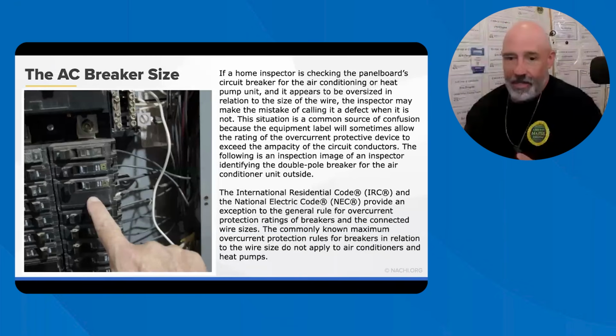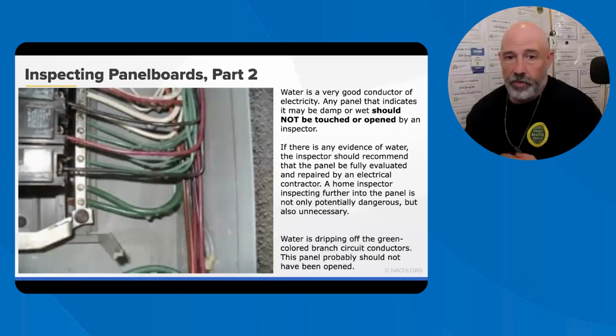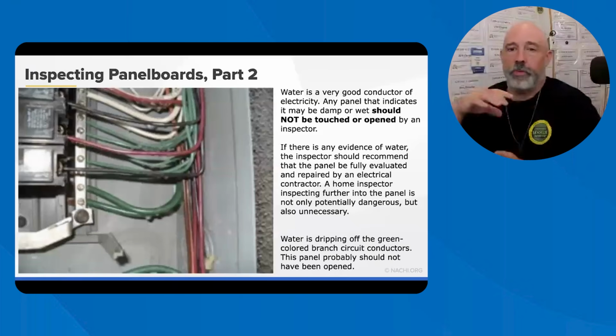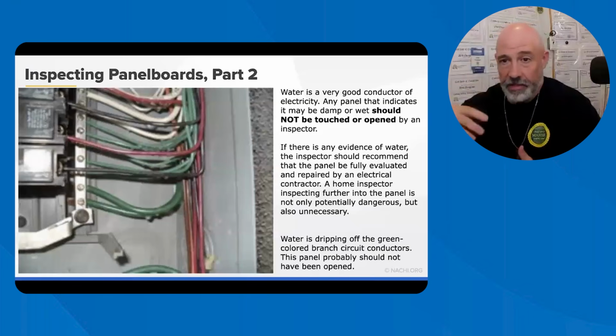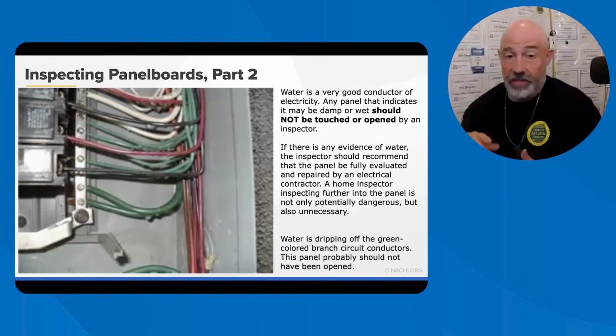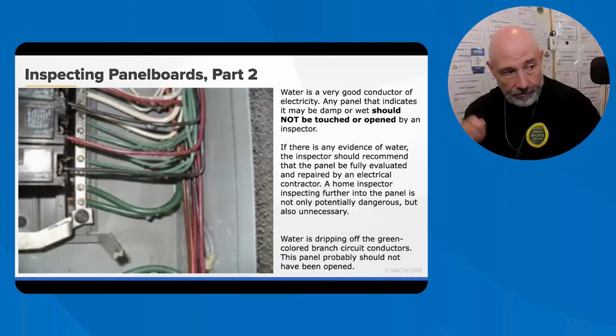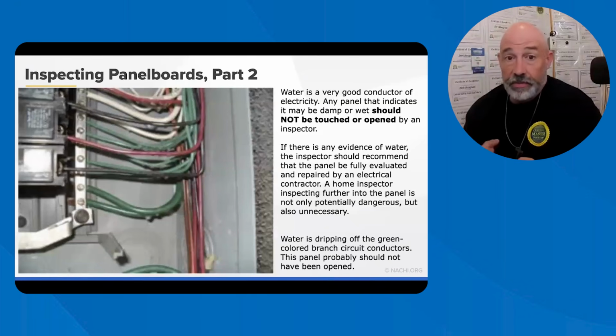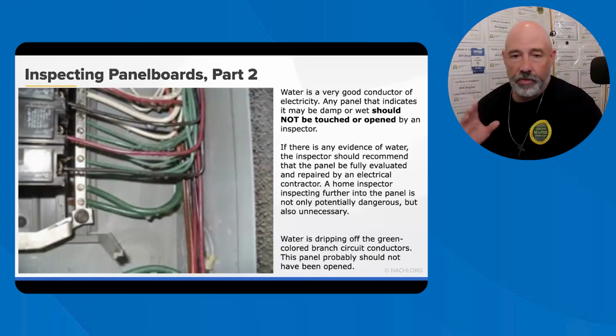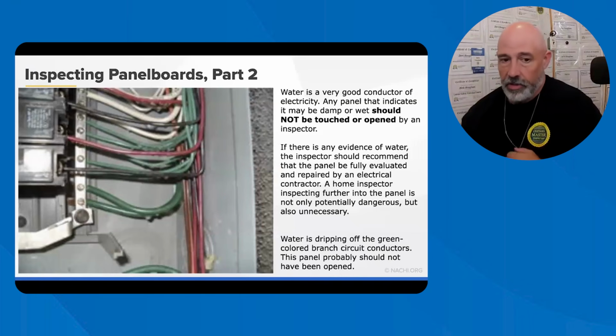But the NEC and the IRC both have stuff for electrical panels, and you can read it on your own if you want, or ChatGPT it or AI it or whatever you want to do. Even before thinking about touching or inspecting or removing a dead front cover, the inspector really should look for those signs of water, moisture, staining, rust, things like that. Feel it with the back of your hand. Make sure that you're not feeling any energy. You can use a sniffer too, and just see what's going on. Any failure whatsoever, if you don't feel safe, make sure further evaluation.